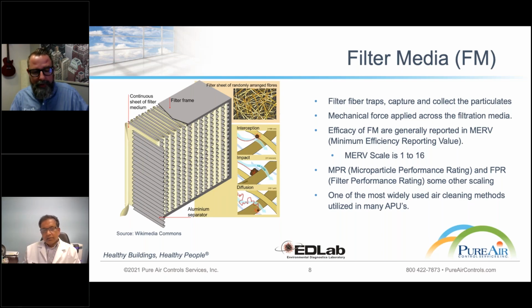One thing I wanted to tell Troy is that HEPA is not always the right solution, and neither is a higher MERV rating always right. HEPA stands for high efficiency particulate air. If you create more restriction, you have to pay more in energy, and many times your goal isn't to restrict particles less than 0.3 microns. At the same time, we're worried about COVID-19 and SARS-CoV-2 — everybody knows their size range is one of the vital issues people and scientists are discussing, and that's why there's a lot more discussion about HEPA and MERV ratings right now.